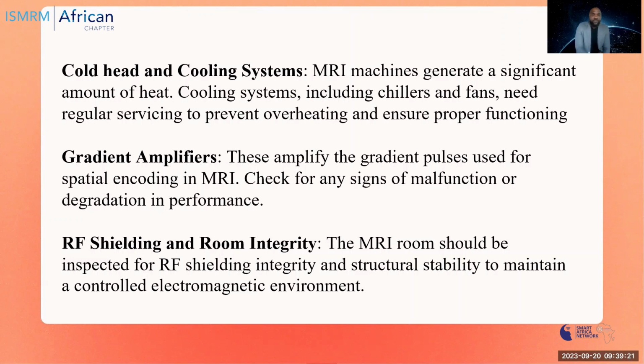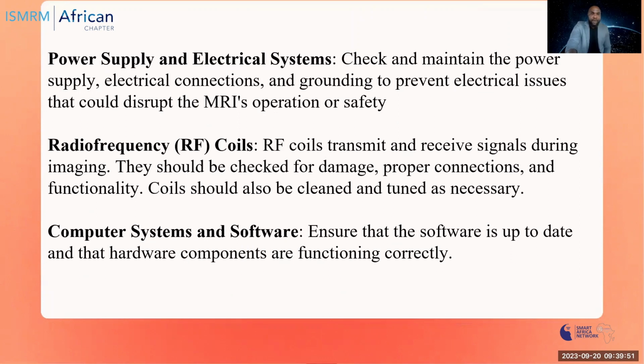Also, the gradient amplifier must be serviced and checked for power, to ensure that the power going to the gradient amplifiers is okay. The integrity of the RF room also must be checked. The doors should be checked to ensure that we don't have any leakage of external interference from outside into the MRI room.